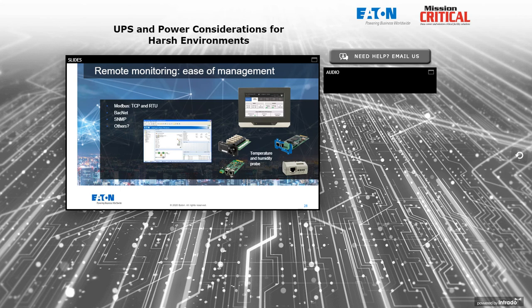This type is very common for a lot of brands of UPSs, and it connects to the UPS with a simple RJ45 connector. And of course, it'll sense temperature and humidity levels; a battery cabinet, for example, is a good place to use that. In addition to its sensing capabilities, this one shown has a couple of dry contact terminals. So if I have a device like maybe a water sensor or a door open alarm that I want to communicate back to the UPS and then onto my monitoring network, I can do that by simply connecting the dry contact wires to my temperature and humidity sensor, and that information will be transmitted back to the UPS along with the temperature and humidity information. So lots of flexibility with these type of devices, and there's a wide variety of them available.